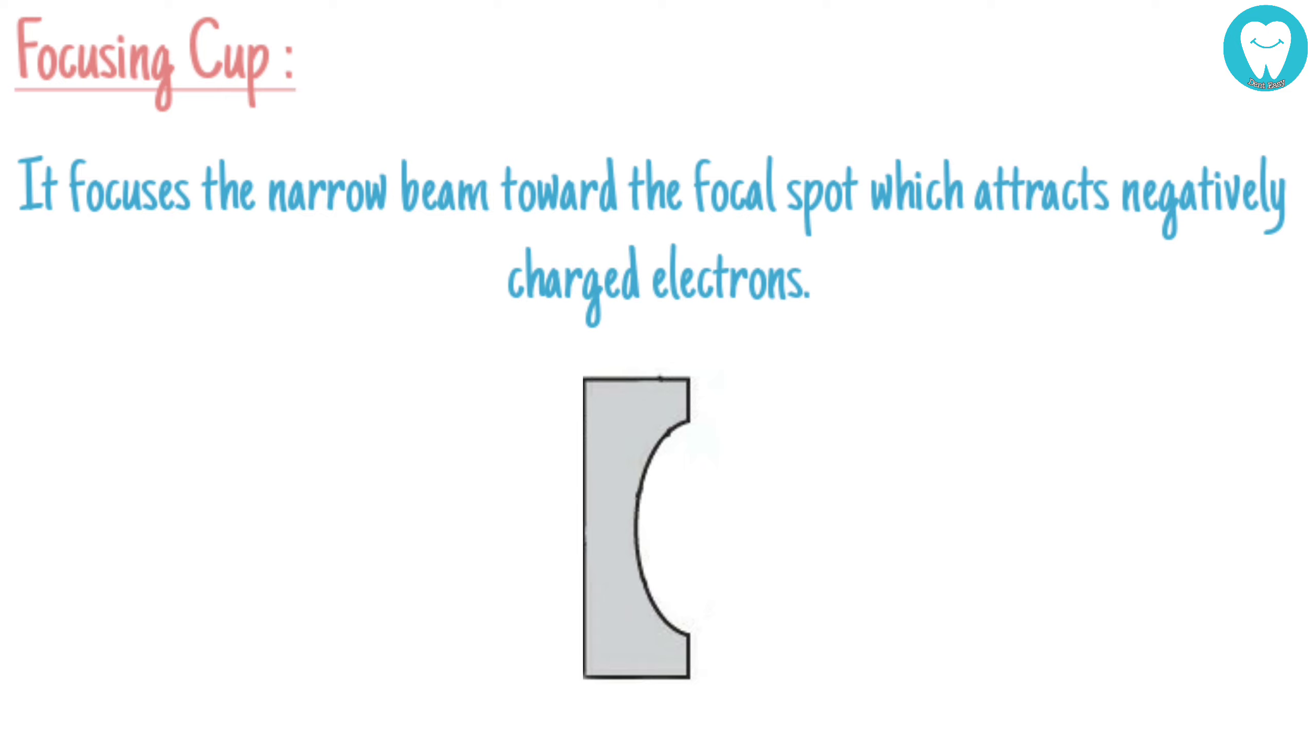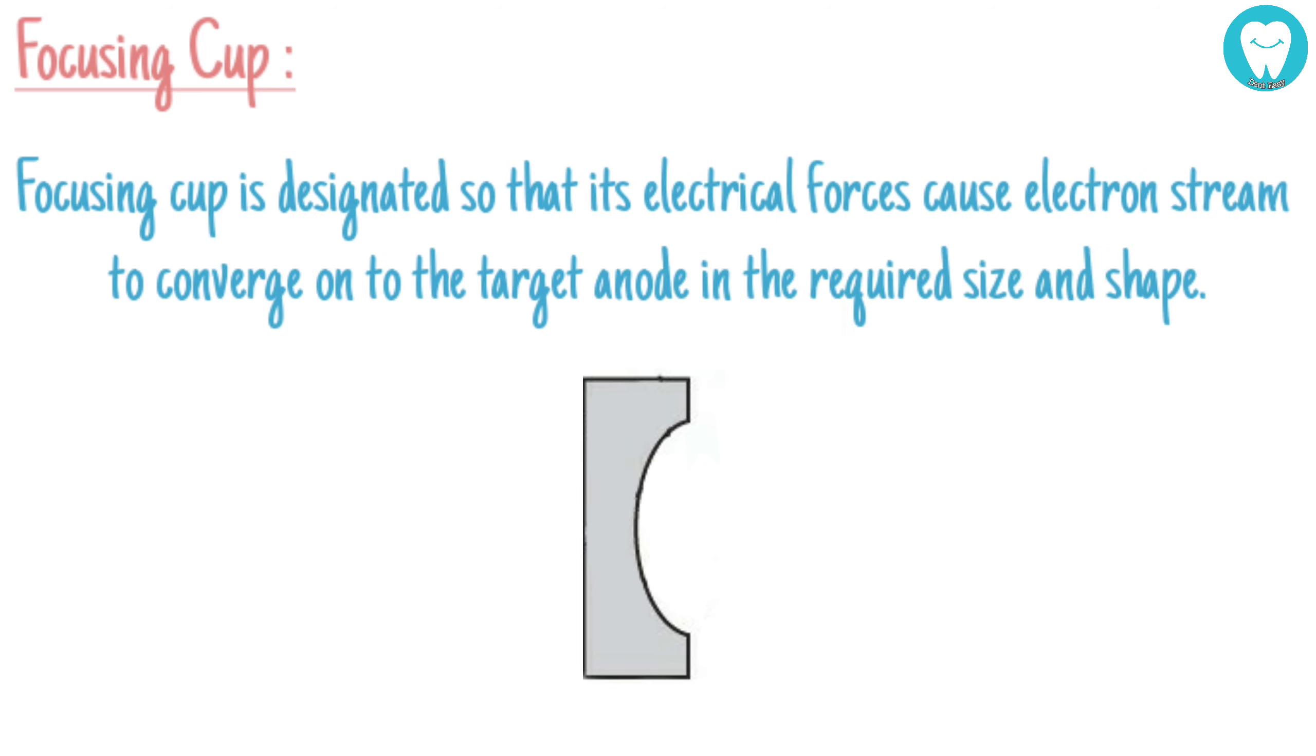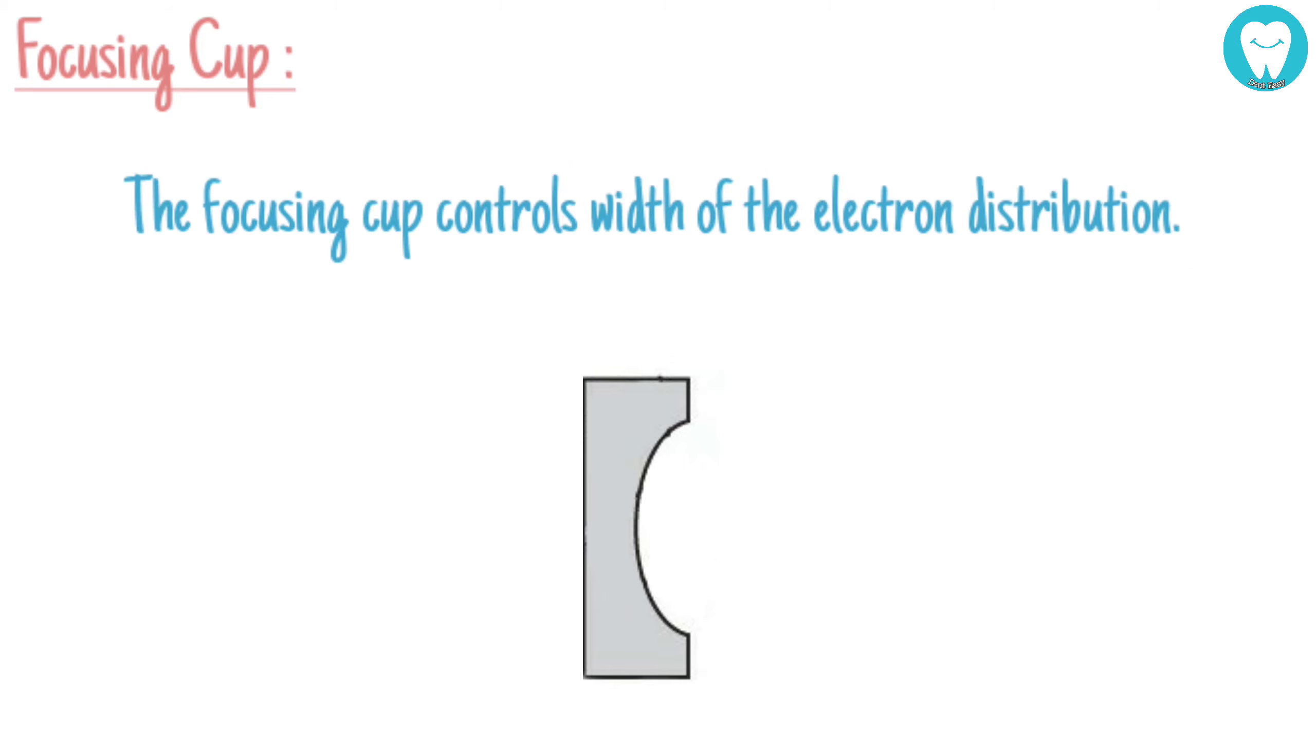The focusing cup is designed so that its electrical forces cause the electron stream to converge onto the target anode in the required size and shape. The focusing cup controls the width of the electron distribution.